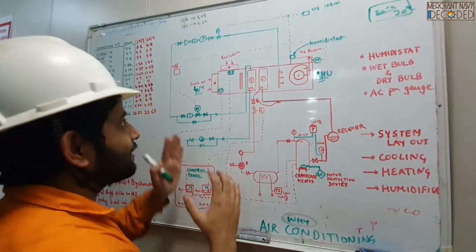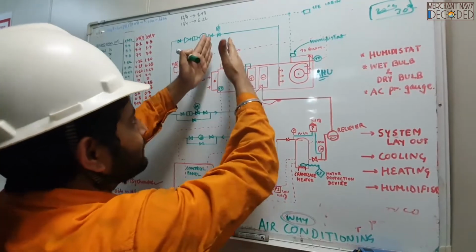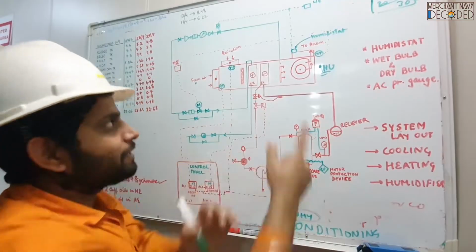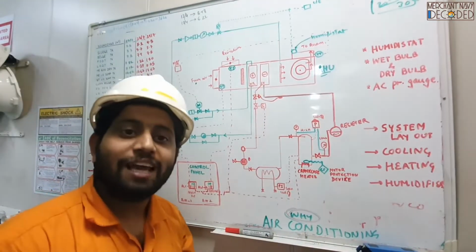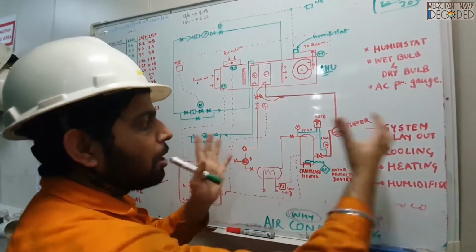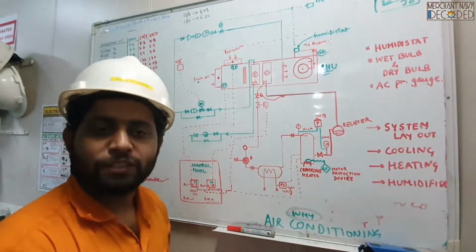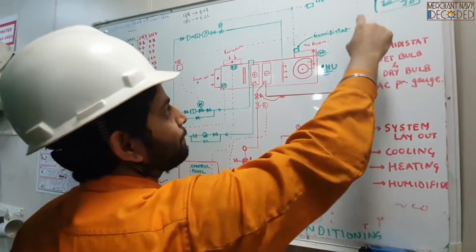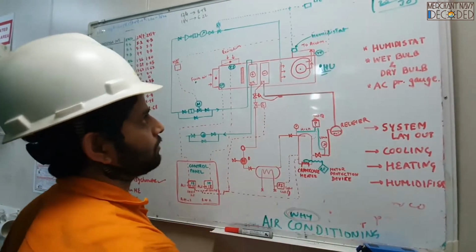So that is why when we are in hot regions, we would want our recirculation to be fully open and the maximum cool air which has already gone into the cabin to come back. So that is how we are maintaining the efficiency of the system. We will not be running all the compressors. Maybe 2 compressors are sufficient to run the AC, right? Understand? To maintain the temperature, say 20 degrees centigrade, at the outlet over here.